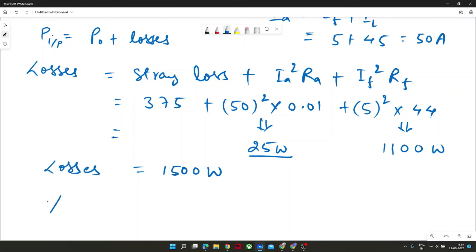And if you can see now, I will write output by 9.9 kilowatt, output plus losses, 9.9 plus 1.5. And let me see, 9.9 divided by 9.9 plus 1.5, it would come out to be 86.8 percent. This is 86.8 percent.